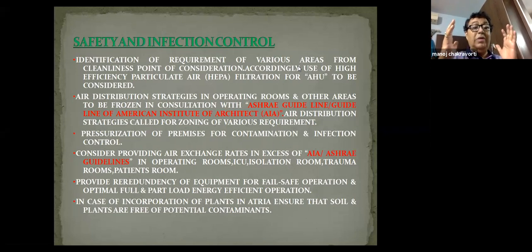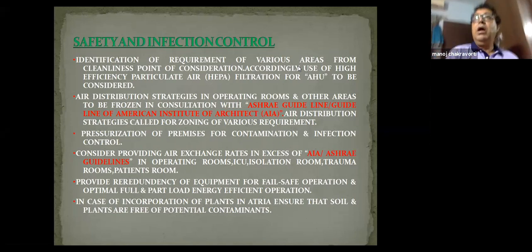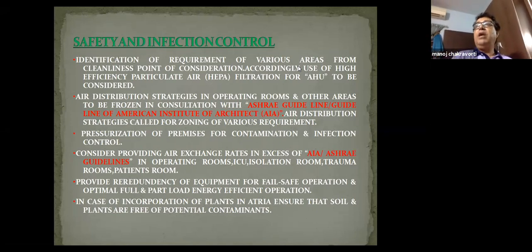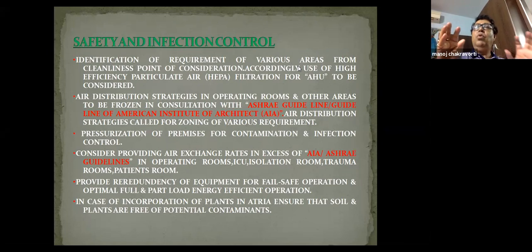So we should always keep those things in mind, even if we want to save energy. Even where 100% fresh air has to be used, I can use a dedicated outside air system, DOAS. Maybe the DOAS initial cost is more, but it saves a lot of power. So we have to apply this in our mind and accordingly select the equipment.